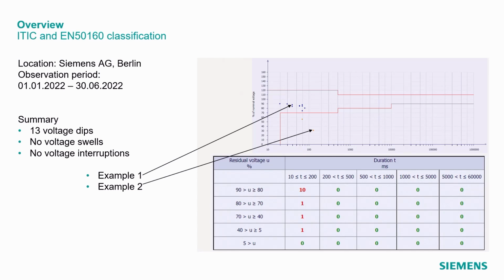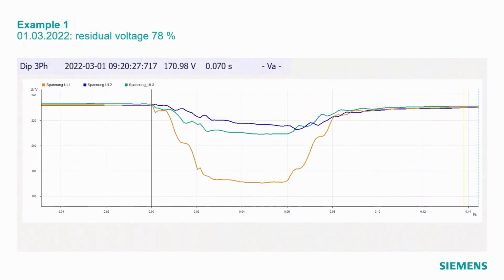So let's have a deeper look at two events now. Event 1 occurred on 1st of March 22. The residual voltage is 78%. It's not so critical. It was quite short, only 70 milliseconds, and only phase A went down to 171 volts. Other phases were not so heavily affected here.